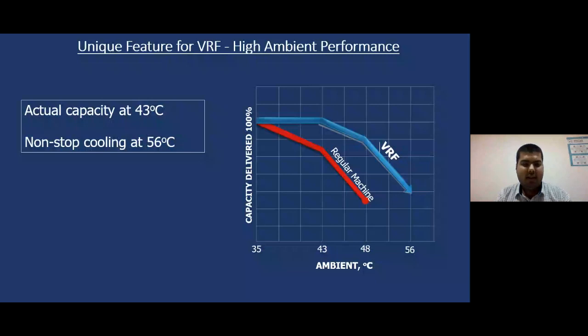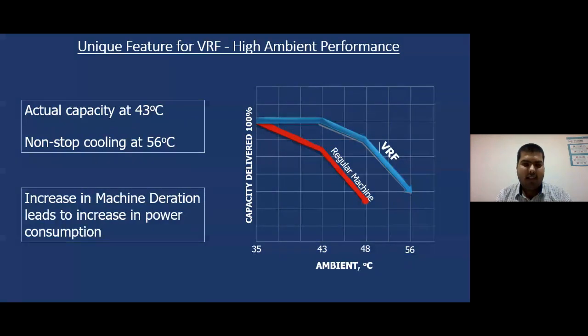In high ambient conditions we go as high as 49-50 sometimes. Thereby the power consumption of the customer is much more reduced when we go for VRF as compared to a regular machine. By regular machine I mean an inverter 5-star split AC also. It is rated at 35 degrees Celsius only, whereas a VRF is at 43 degrees Celsius. Increasing machine derating leads to increasing power consumption, as I explained. So a VRF would give much lower cost, leading to much lower power consumption. And for a regular machine, the power consumption would increase, thereby increasing the cost for the customer.